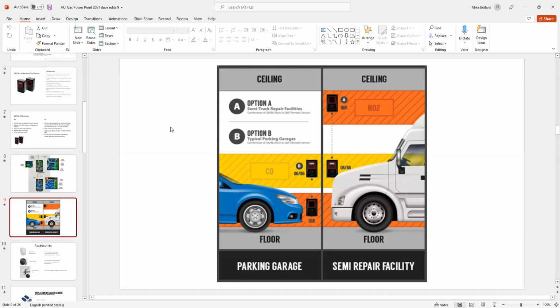This is just a standard way of mounting in a parking garage: your typical Q6 or B6 right here, with the NO2 and CO sensor down low, and CO at 5 to 6 feet. It all depends on the application. If you're looking at a loading dock, for example, and the semis backing in have stacks that blow the air straight up, you may want to mount your NO2 sensors 2 feet off the ceiling, just in case. If they're semis that have floor-type exhausts, you may need both, or maybe just the floor, depending on where the exhaust is coming out.